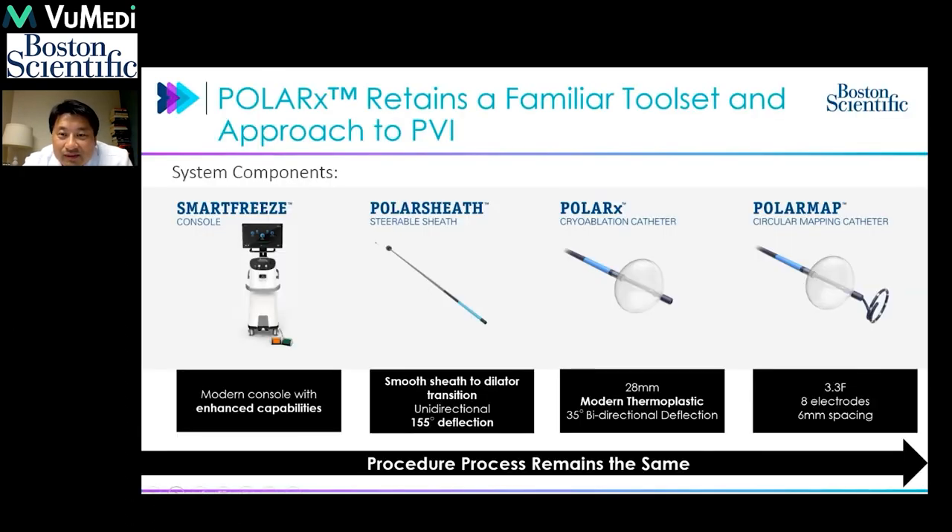The Polar Rx system is a very familiar toolset compared to the existing cryoballoon system. The components include the Smart Freeze console that controls the cryoballoon injection and freezing cycle, the Polar Sheath which advances the cryoballoon into the intended target, the Polar Rx cryoballoon catheter itself in a 28mm design with a 31mm option, and the Polar Map mapping catheter that comes in front of the catheter to monitor time to isolation.